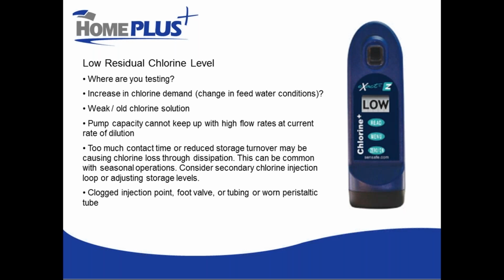The foot valve is the little one-way valve that sits at the bottom of your solution tank where you draw the chlorine solution. That little foot valve can get crystallized mineral deposits on it, especially if you're running high concentrations of chlorine or you're mixing it with water that has minerals in it. Clean that foot valve off so chlorine can pass through it readily into the tube, and check the tubing itself for any deposits. That tubing is incredibly cheap, and replacing it every year or so is well worth it to prevent problems.